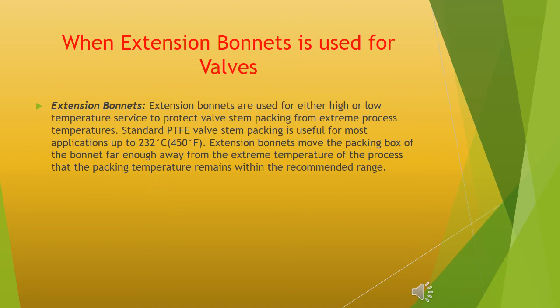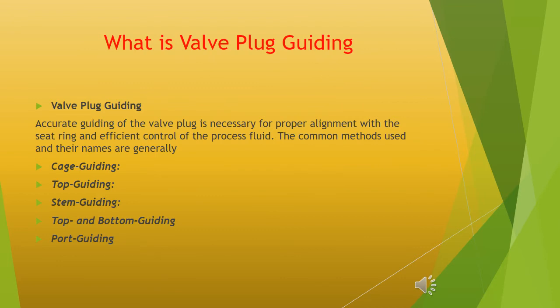When are extension bonnets used for valves? Extension bonnets are used for either high or low temperature service to protect valve stem packing from extreme process temperatures. Standard PTFE valve stem packing is useful for most applications up to 232 degrees Celsius (450 degrees Fahrenheit). Extension bonnets move the packing box of the bonnet far enough away from the extreme temperature of the process so that the packing temperature remains within the recommended range.